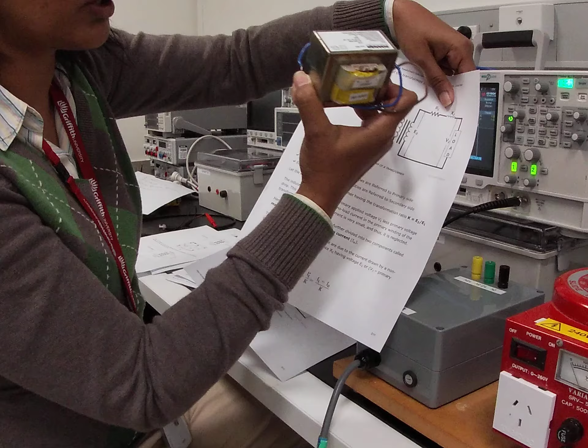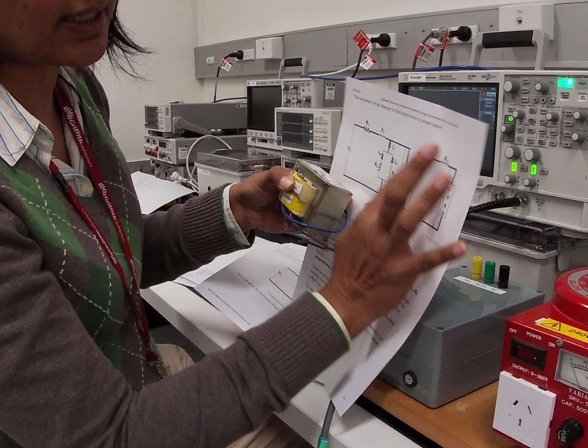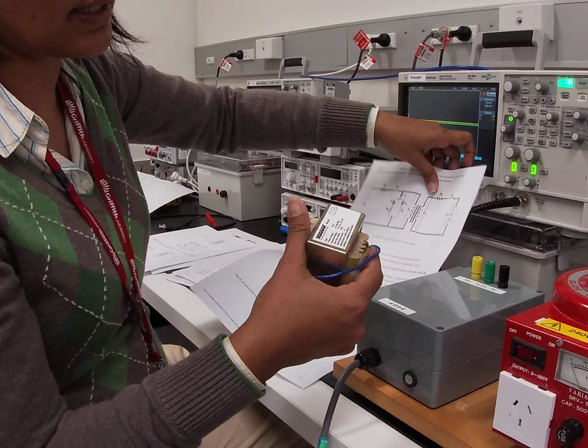So we are only measuring the core resistance and reactance. You can see that there is another winding, the secondary winding, represented by this circuit R2 X2. When we do the short circuit test, we are actually measuring this resistance and reactance value.